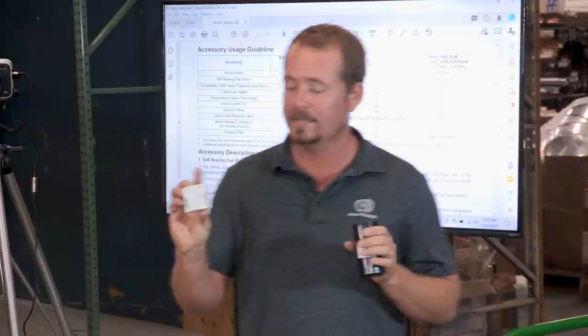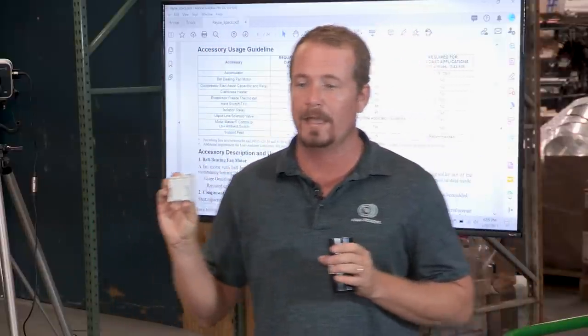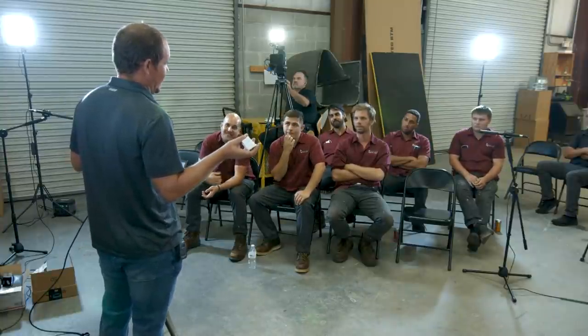What would happen if this was sized so that it came out too quickly? So the contacts open too soon. What would that do? Yeah, it would render the start capacitor less effective, right? And that's what most universal start kits do, because they want to be safe, right?